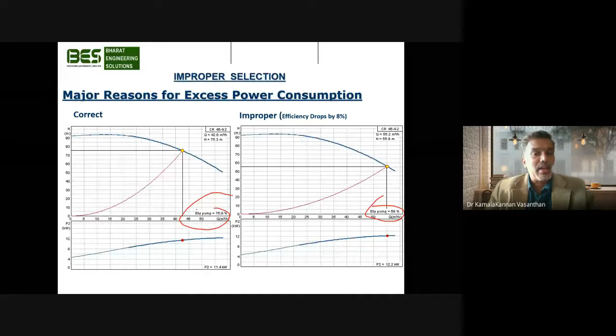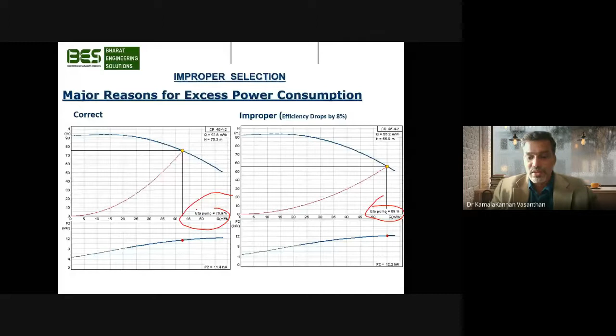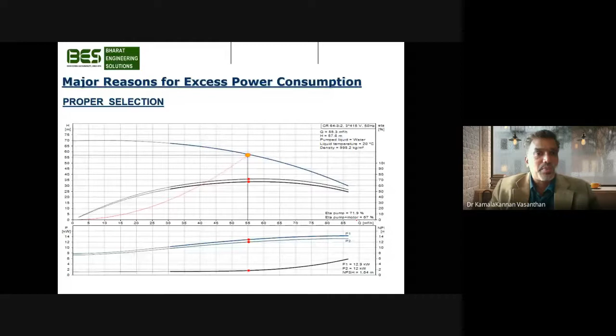The future of customization in supply is growing, and 95% of what we supply goes out customized. Either there's a trimming of impellers, a change of motor power, or an increase in the size or thickness of the casing. Every site is unique and needs to be customized for that particular site. This is the key reason for excess power consumption that we see. For example, for the same 55.2 meter cube and 55 meters, this was the model that should have been selected, which has an even higher efficiency of almost 72%. So the selection of pumps, or any machinery, plays a key vital role in supply, installation, and selection decisions. Thank you.